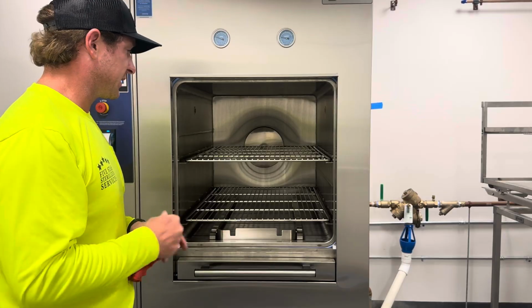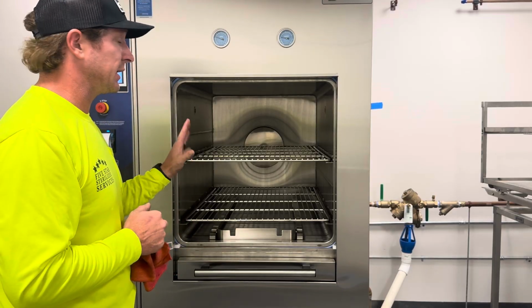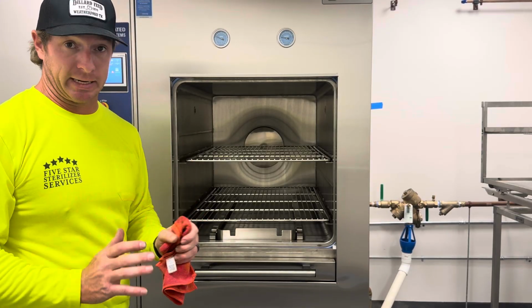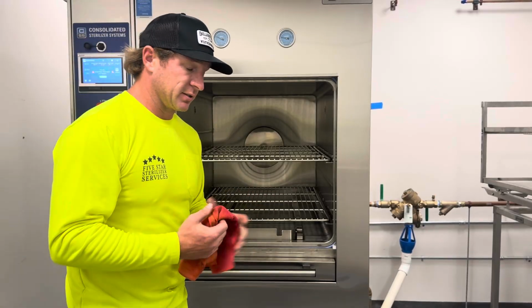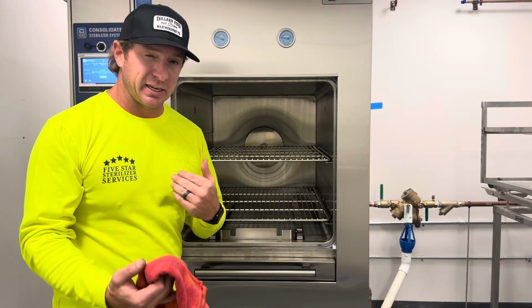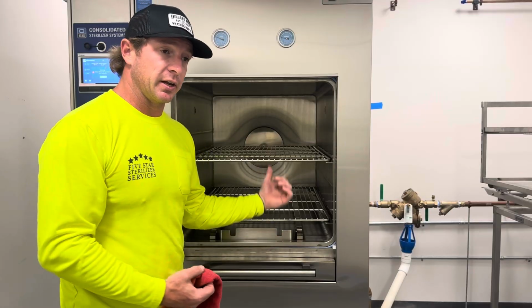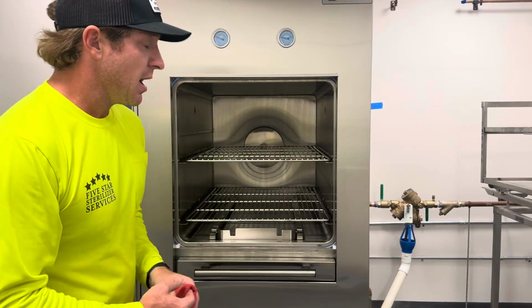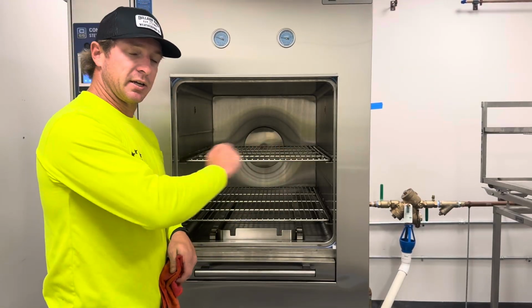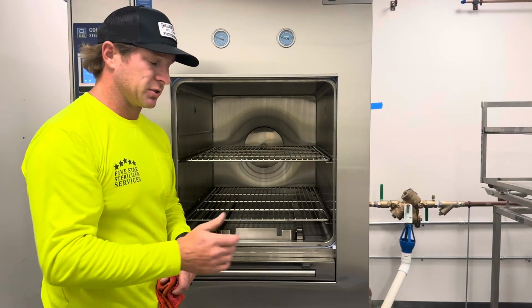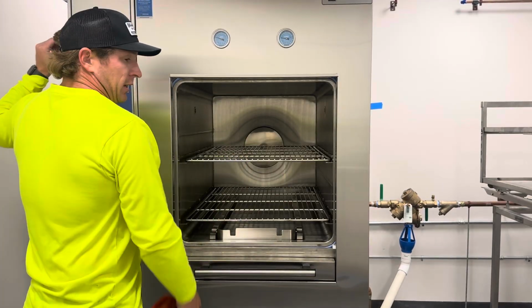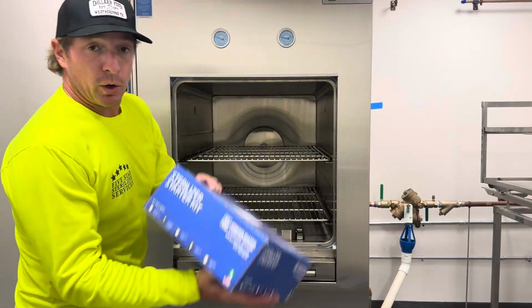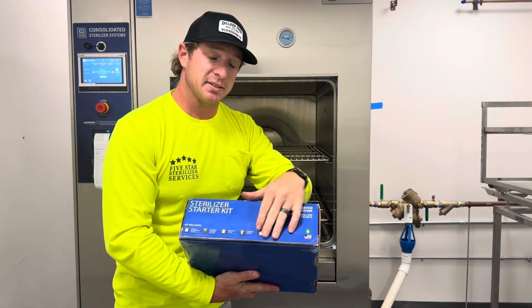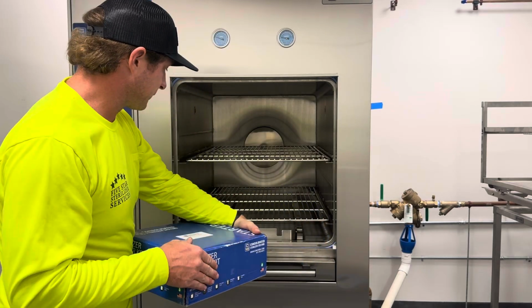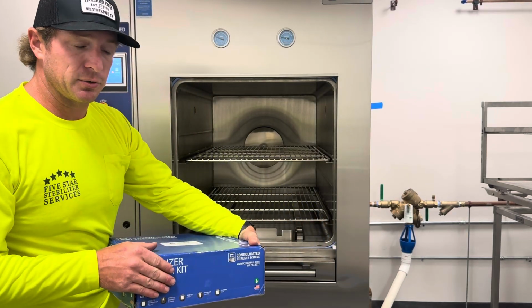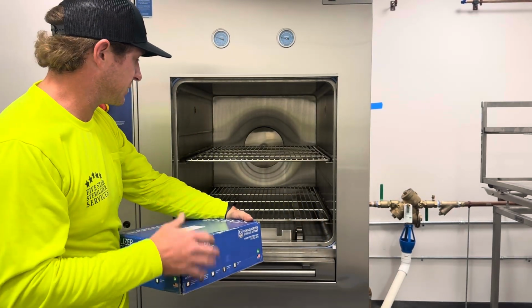Very important. The second most important thing for this machine is not to use any bleach or chlorides. We understand that you might have some bleach or chlorides in your load if you're going to use this for trash, and that is fine. But what we mean is we don't want you to spray this machine down and then wipe it clean with bleach. People think that stainless steel won't rust, but introduce chlorides to stainless steel and it'll start rusting immediately. So please do not use bleach or chlorides to clean this machine.